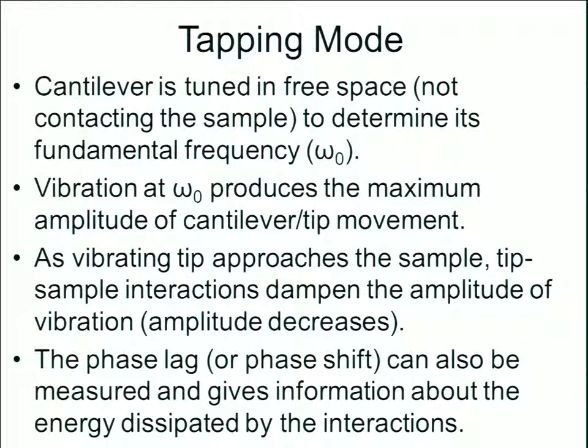The cantilever will be tuned in free space before you start your scan — it does not contact the sample during this step. This is done to determine its fundamental resonant frequency. We modify the voltage to the piezoelectric to vibrate the cantilever at different frequencies, and the one that produces the maximum amplitude is set as the drive frequency.